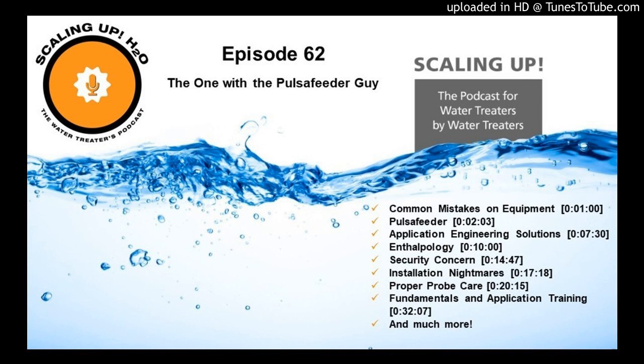Probably one of the things I see the most is probe installation, specifically the pH and ORP probes. If you ever deal with something ion specific, those probes are very finicky. They want water within a certain pressure range, temperature range, and flow range, and you're expected to whip that up out of thin air and make it work. These are real world processes, but I'll comfortably see 10 to 20 gallons per minute going across a pH probe, and that probe isn't going to last near as long as if you installed it with its recommended 3 to 5 gallons per minute. So yeah, that's probably the one that causes the most issues.